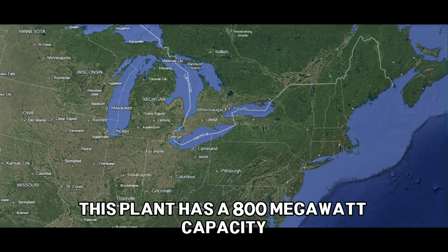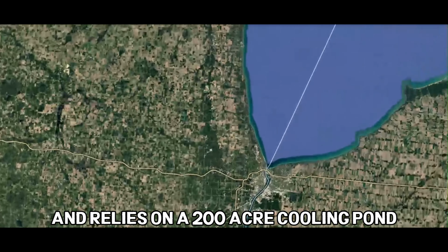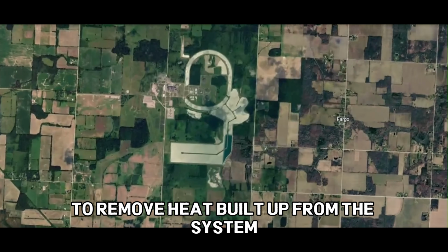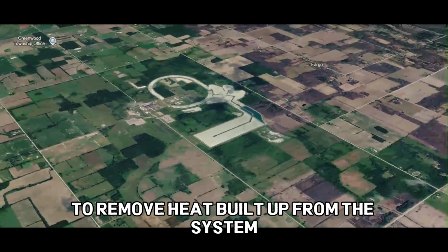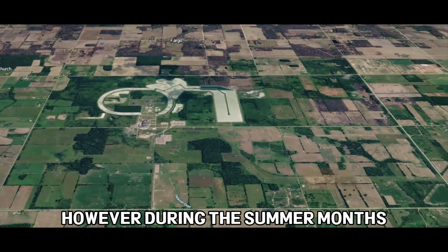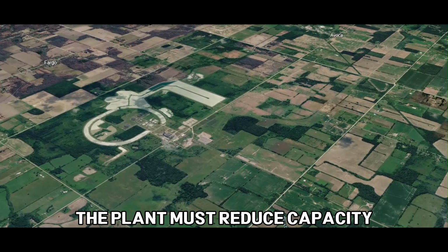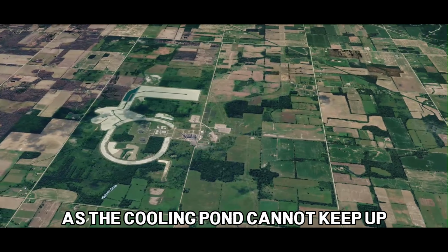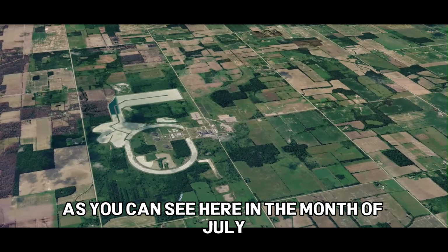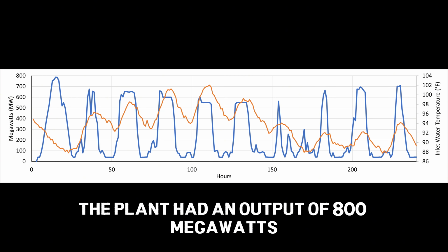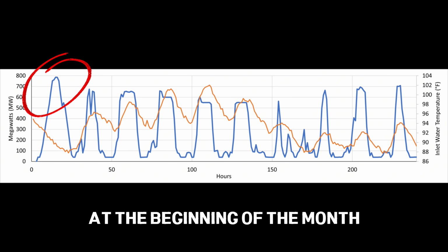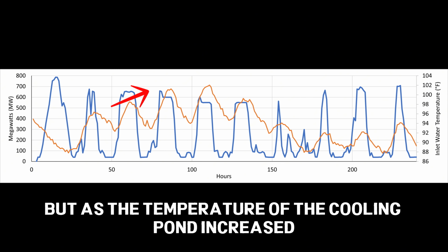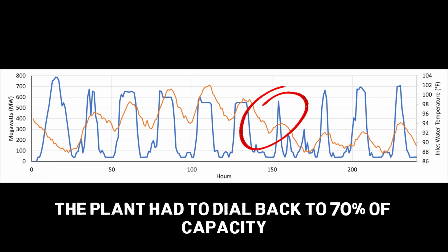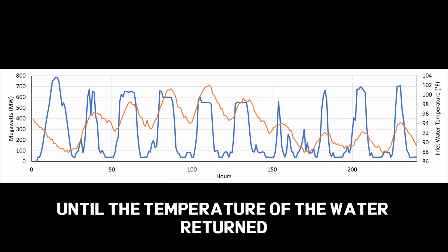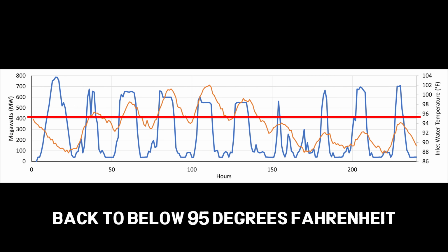This plant has an 800 megawatt capacity and relies on a 200-acre cooling pond to remove heat built up from the system. However, during the summer months, the plant must reduce capacity as the cooling pond cannot keep up. In the month of July, the plant had an output of 800 megawatts at the beginning of the month, but as the temperature of the cooling pond increased, the plant had to dial back to 70% of capacity until the temperature of the water returned back to below 95 degrees Fahrenheit.